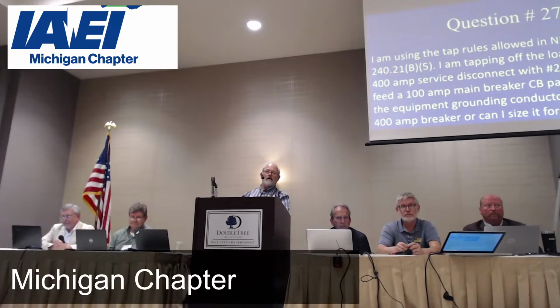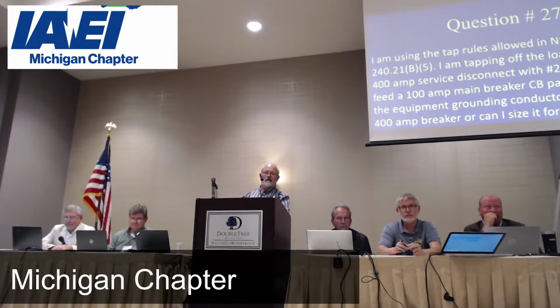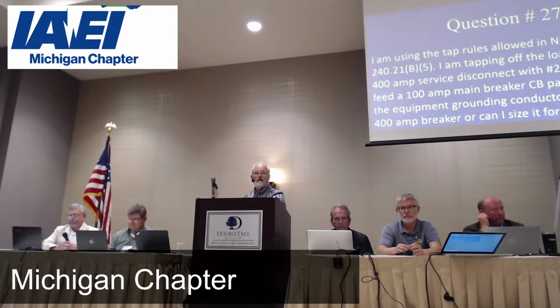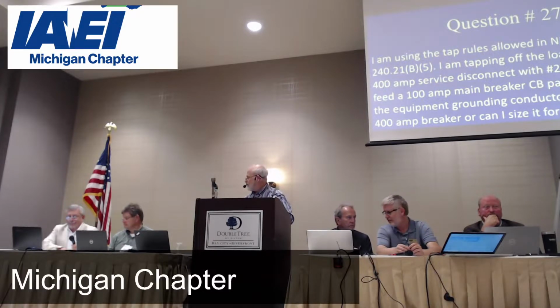Questions or comments? Yeah. Go ahead. Yeah, I do think the intent, I was on code panel 5 when this wording went in. The intent was, there was no sense having an equipment grounding conductor to clear a fault larger than the conductor supplying the fault, which in this case would be the number 2, because this is an extension to that piece of equipment, that's the 100 amp. So in other words, the fault would be going through the number 2, off to the ground, returning on a number 2 equipment ground. Yep.